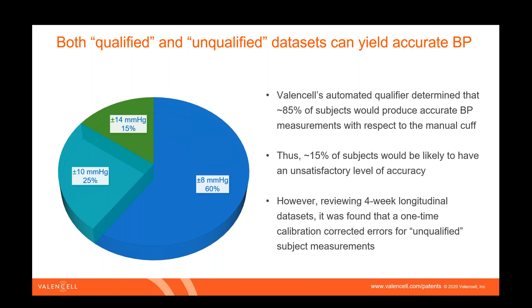And we looked at the longitudinal data we had collected. We have several data sets where people have come in for a few weeks, in some cases months or longer, and we saw, okay, how well would we do? We did an initial calibration of these folks. How well would we do? And we found that when we did that, the stats for these people was plus or minus 10 millimeters of mercury. So what that means is, with what we have today, what I can say with 100% certainty today, is that 85% of people who are tested are going to see that their statistics are within plus or minus 10 millimeters of mercury. 15% are not going to get that, but with a one-time calibration, they will get that.